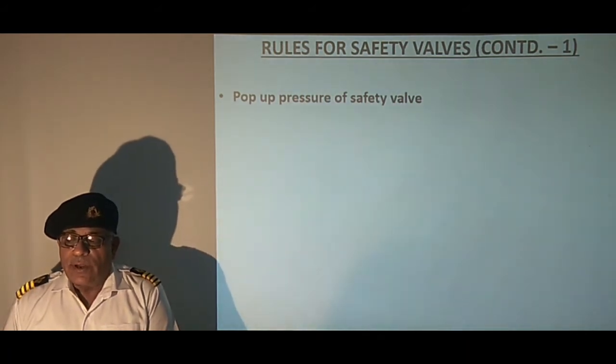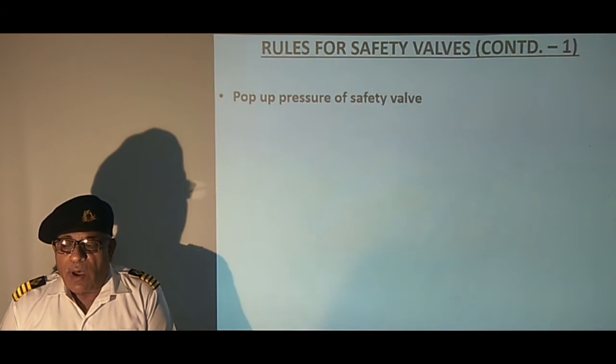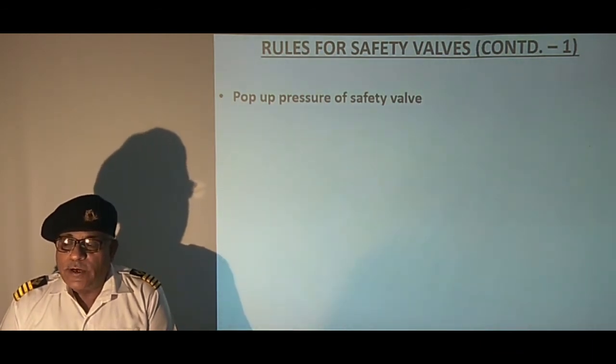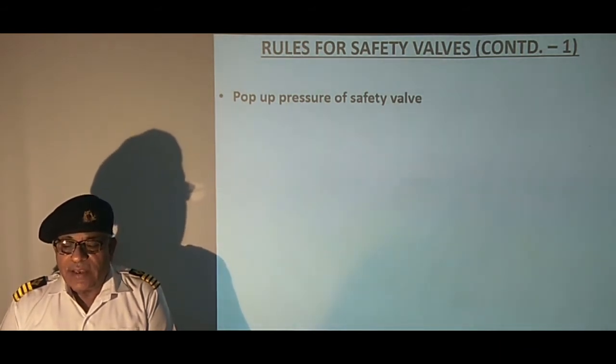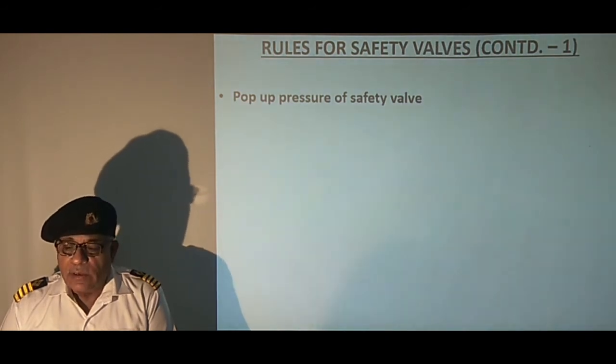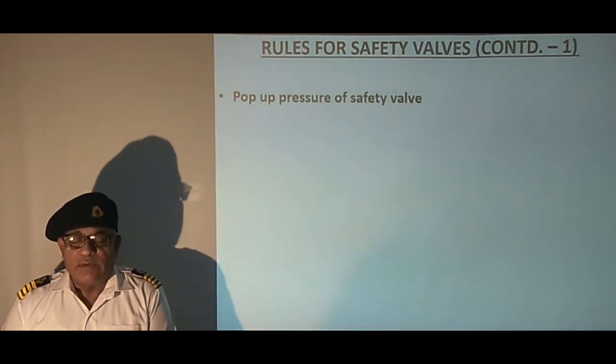For the same reason, the superheater safety valve should be set to close last. The superheated steam safety valve should be set as close as possible to the operating pressure, otherwise expansion can affect the correct operation of the safety valve.